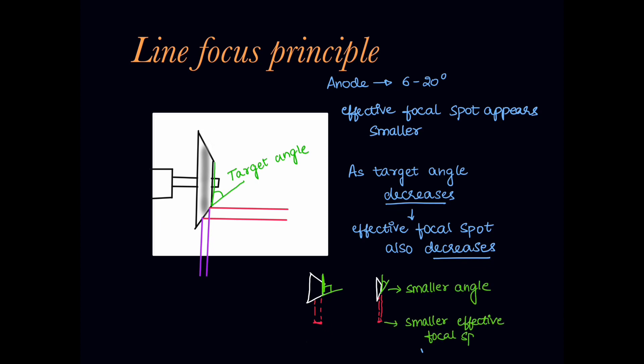As the target angle decreases from 20 degrees to 6 degrees, the effective focal spot size also decreases. Here we can see the smaller the angle, smaller the effective focal spot.